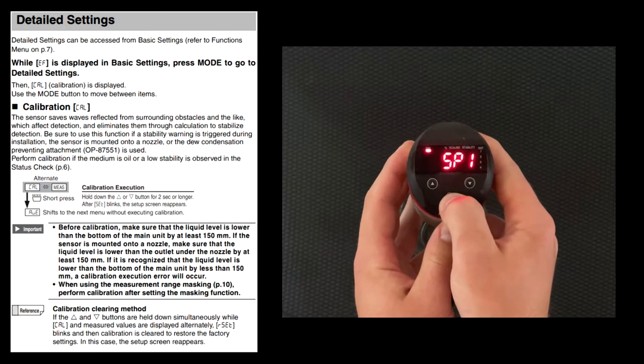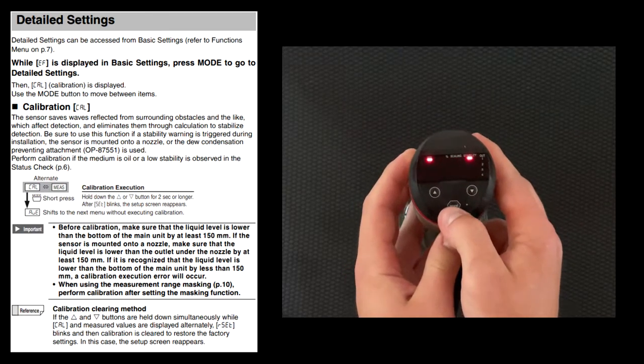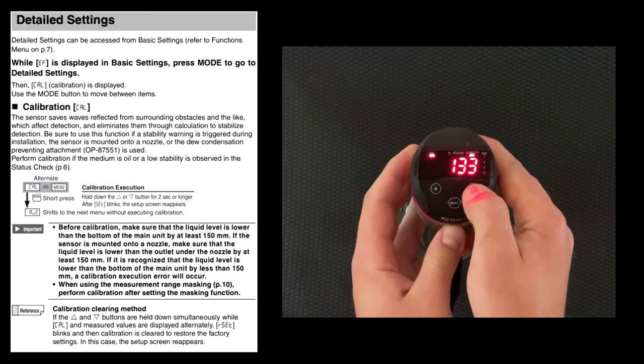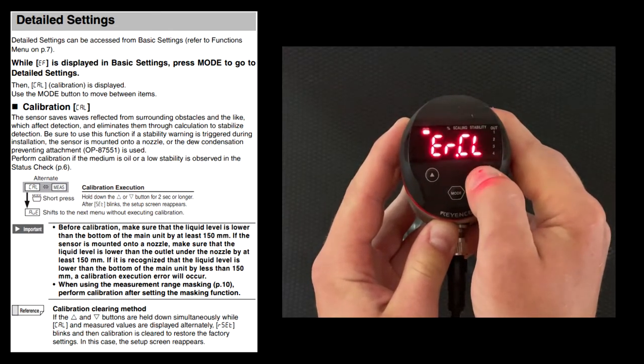Adjusting the installation location of the FL may be necessary if, when performing a calibration, you receive an ERCL error, or calibration error, as you can see on the screen. Just follow those instructions we talked about at the beginning to give yourself the best chance of performing a proper calibration.